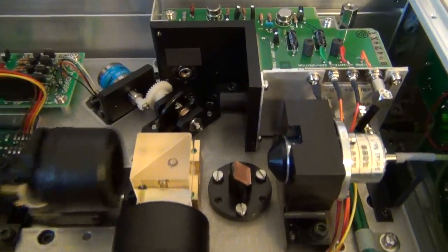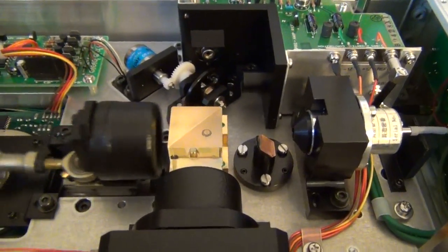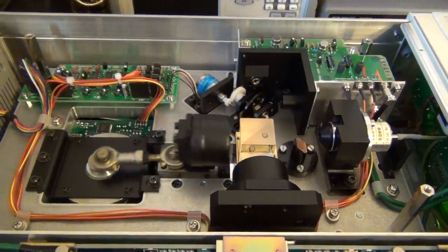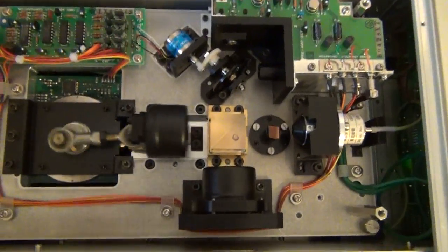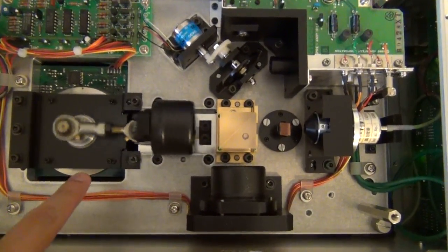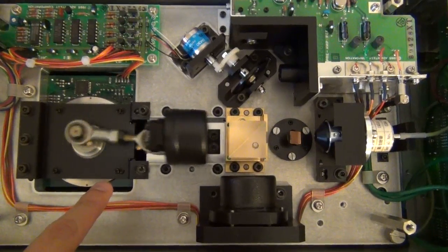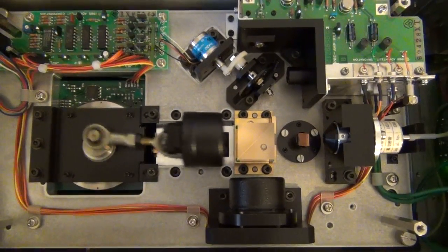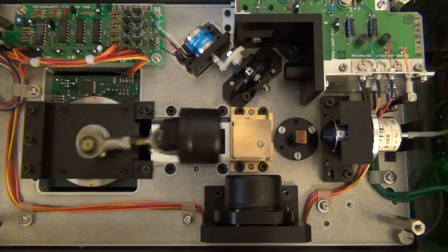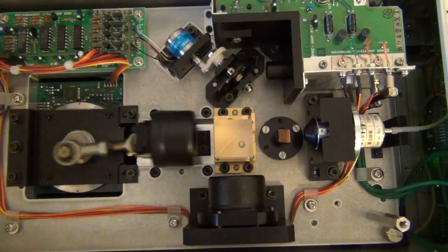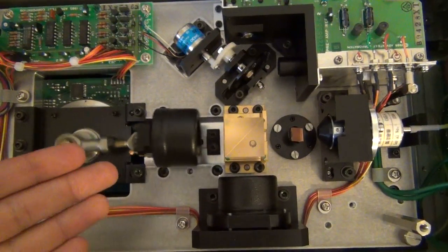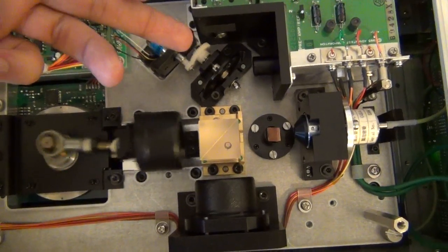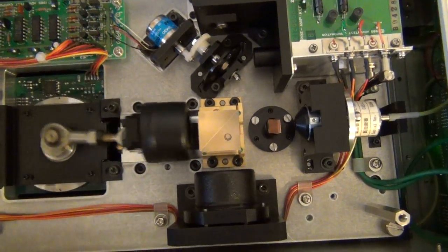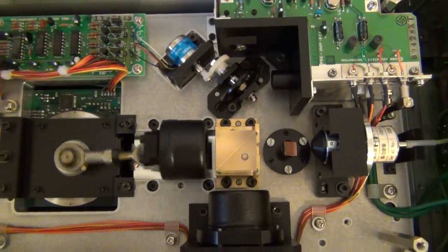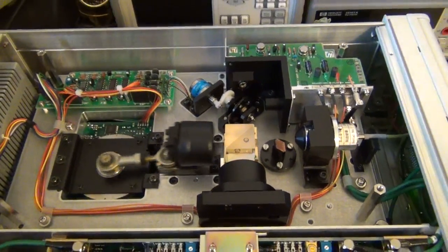So that laser is actually mounted on the opposite side of the instrument. So I'm going to open the opposite side of the instrument so you can see that. If you think about it, the instrument always knows the position of this mirror because it uses a stepper motor, so it can always tell where the mirror actually is. So by measuring correlation between the position of the mirror and the detector on the sensor there, it can find the wavelength. So let me turn it around and open the other side so you can see the laser itself.